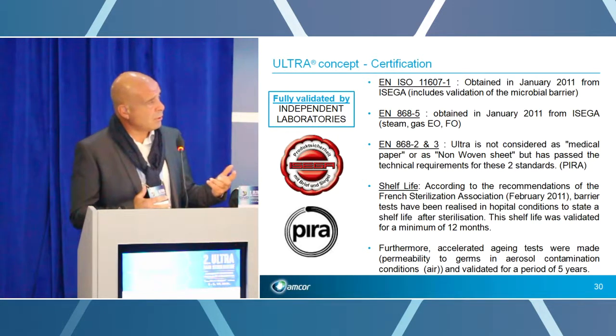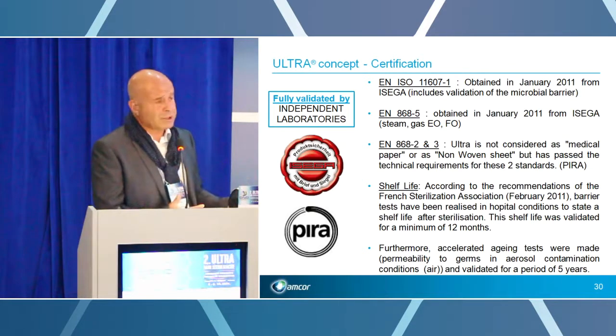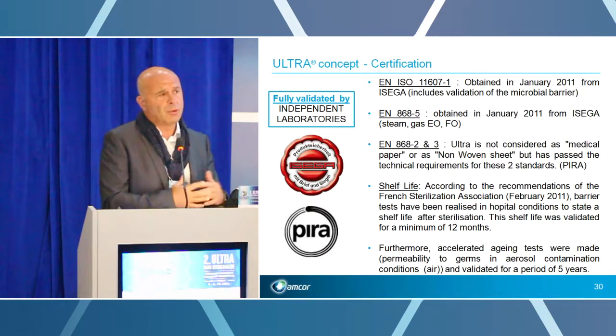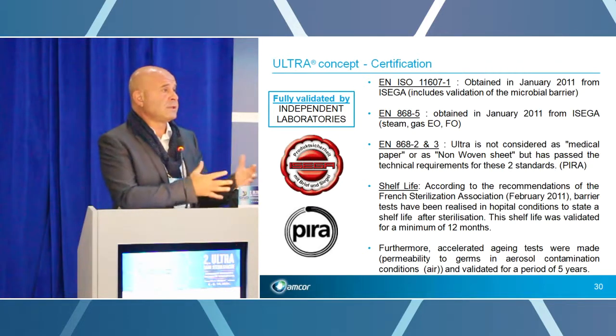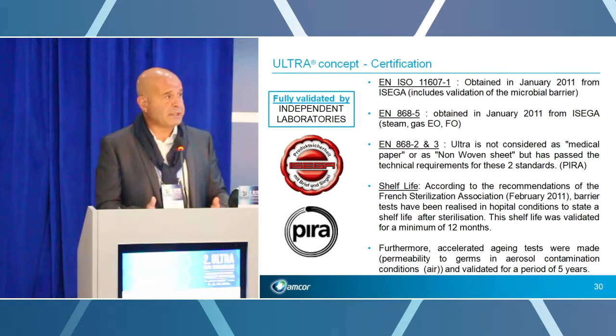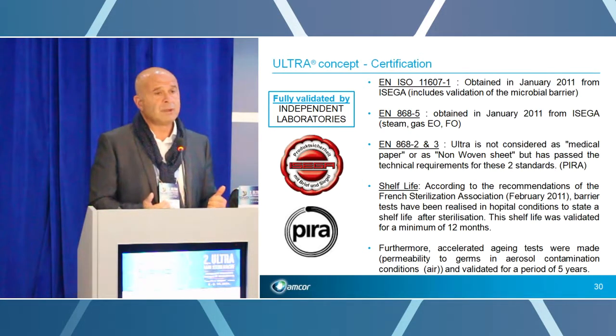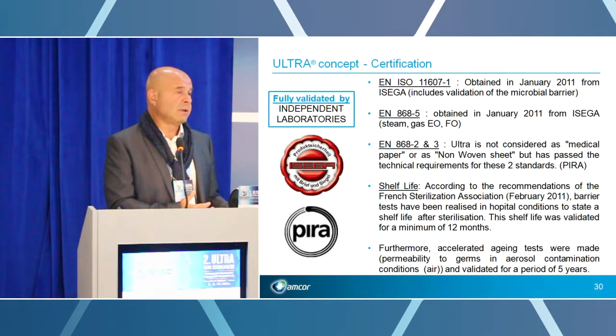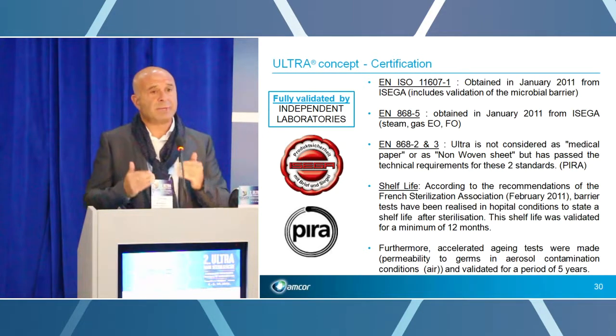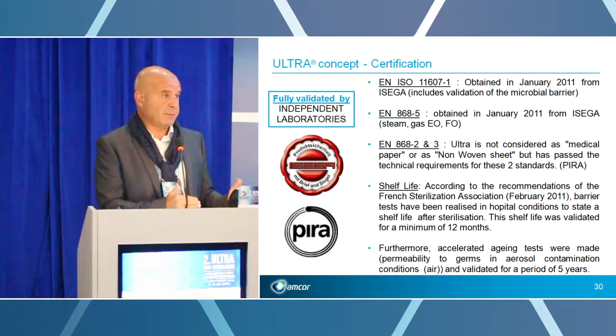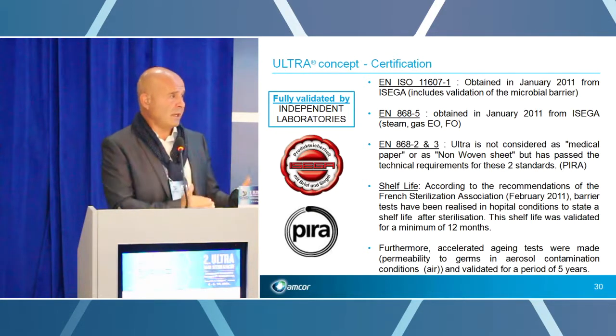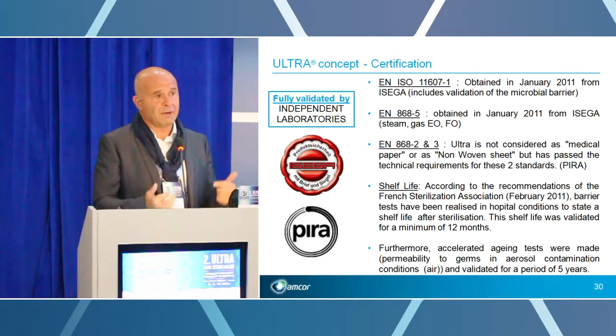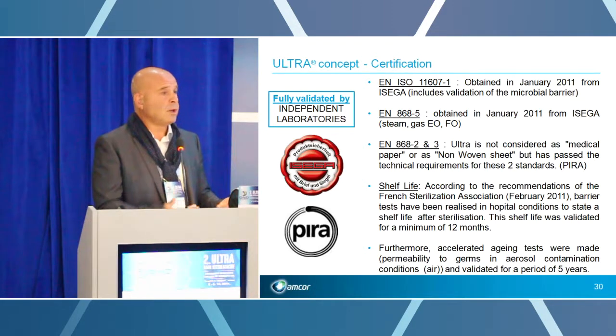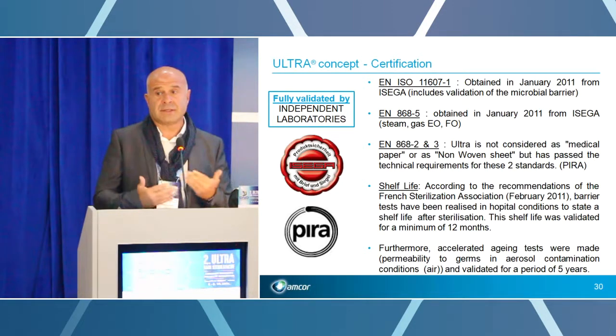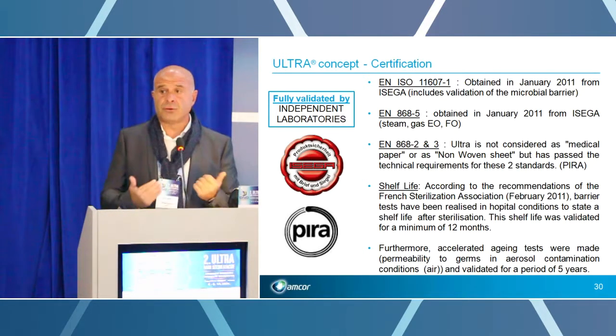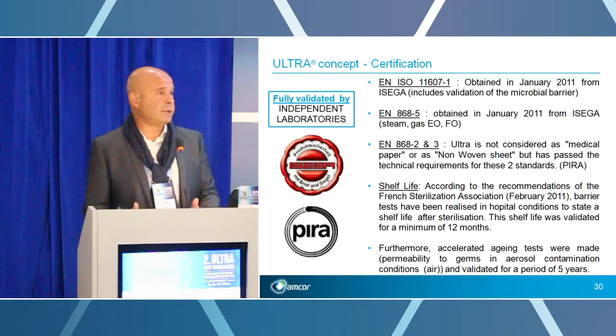It's possible to package all you want. It's possible to use single packaging or double packaging, because all the tests we did are for single or double packaging. Ultra is an SBS, a sterile barrier system. Okay? Single is a single sterile barrier system. And after, you choose, in function of the risk analysis in your CSSD and operating theater, whether you do single packaging or double packaging.